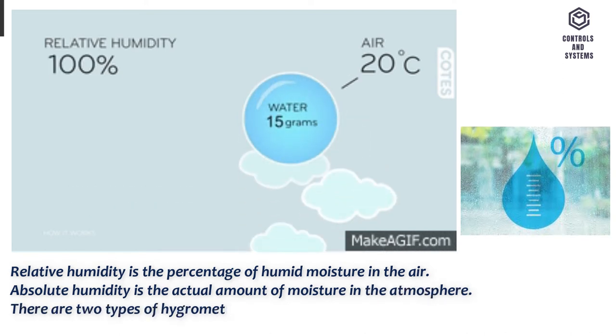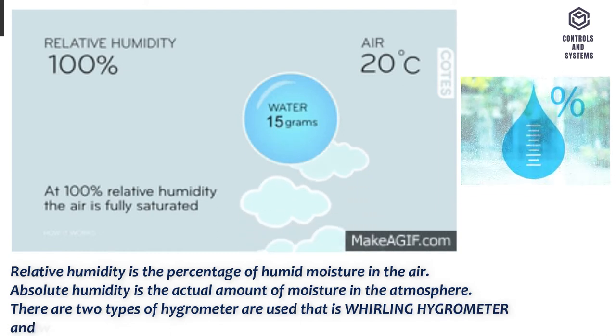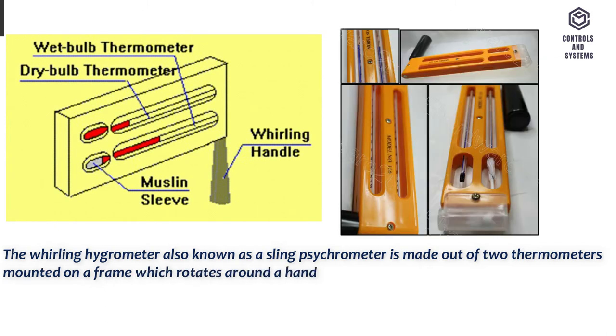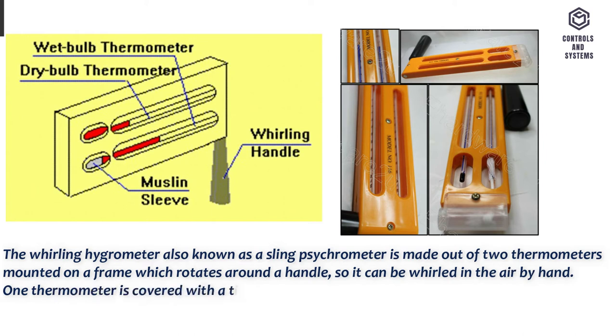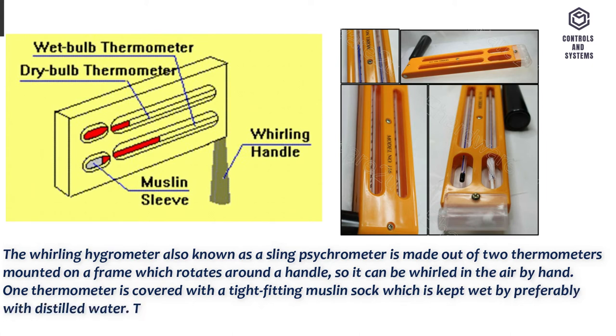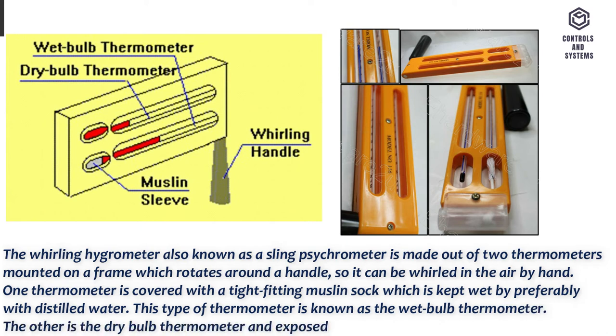There are two types of hygrometer used, that is whirling hygrometer and wall mounting hygrometer. The whirling hygrometer also known as a sling psychrometer is made out of two thermometers mounted on a frame which rotates around a handle, so it can be whirled in the air by hand. One thermometer is covered with a tight fitting muslin sock which is kept wet, preferably with distilled water. This type of thermometer is known as the wet bulb thermometer. The other is the dry bulb thermometer and exposed to the atmosphere directly.